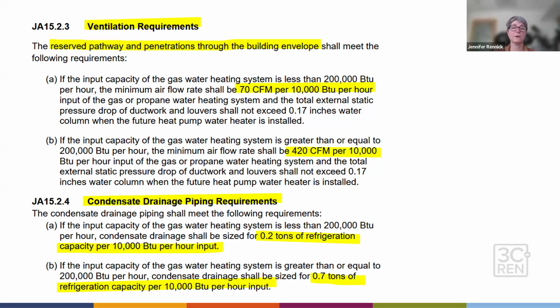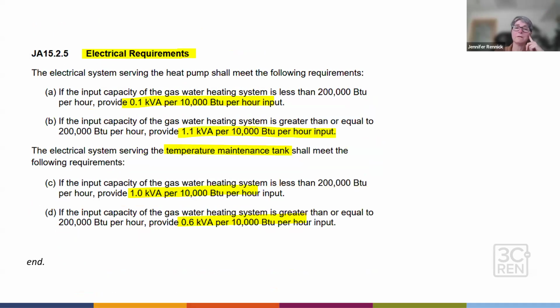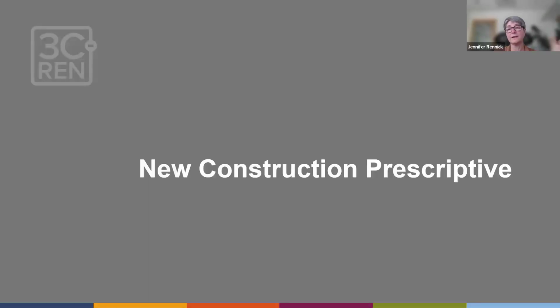And then it goes on from there with the condensate drain piping requirement based on the tons of refrigeration capacity that you would be able to drain, again, based on whether it's bigger or smaller than the 200 kBTU per hour capacity. And then the electrical requirements follow a similar pattern. If it's less than or more than the 200 kBTU, and again, then the kVA requirements for both the heat pump and the temperature maintenance tank, sometimes called a loop tank or recirc tank, are also based on those same requirements. But this gets into the meat of what is supposed to be designed for. So that's there for your reference.